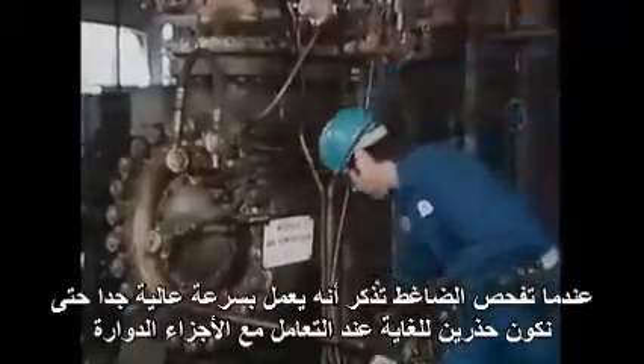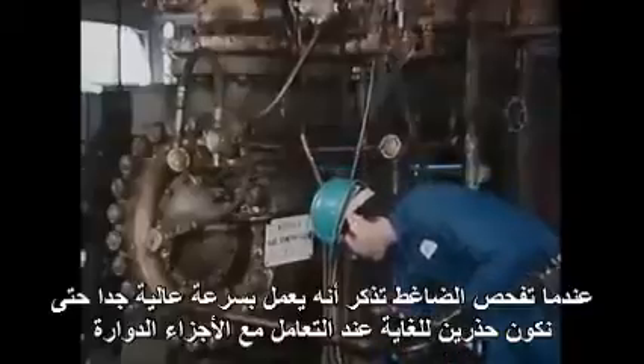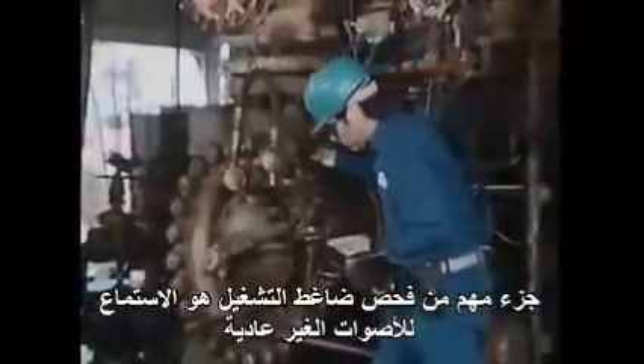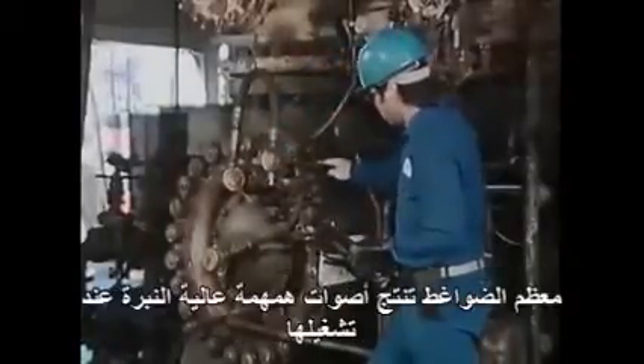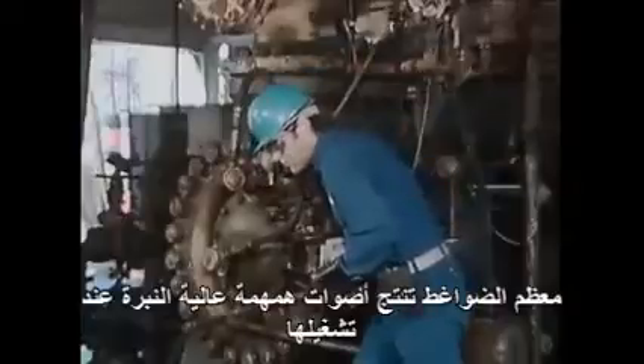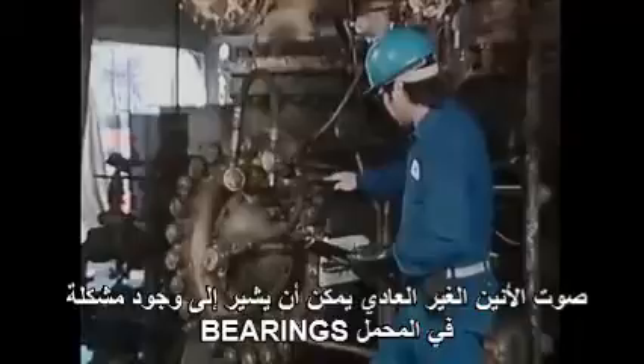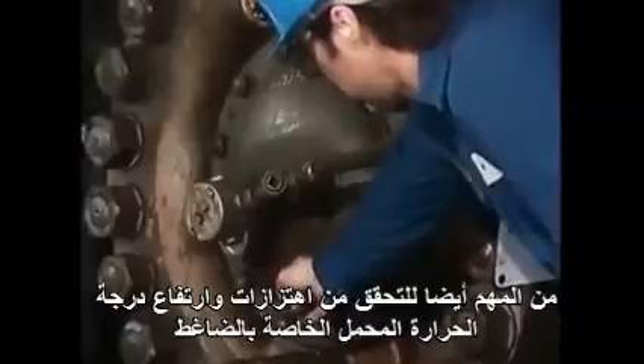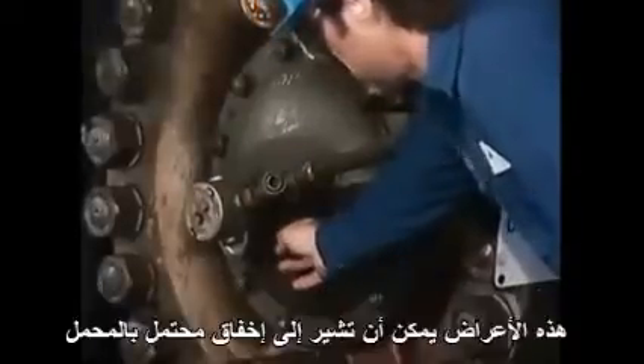When you're checking a compressor, remember that it operates at a very high speed, so be extremely careful when you're working on one that's running. An important part of checking an operating compressor is listening for unusual sounds. Most compressors produce a high-pitched hum when they're running. An unusual raspy or squealing sound can indicate a problem with a bearing. It's also important to check the compressor's bearings for excessive vibration and overheating. These symptoms can indicate a possible bearing failure.